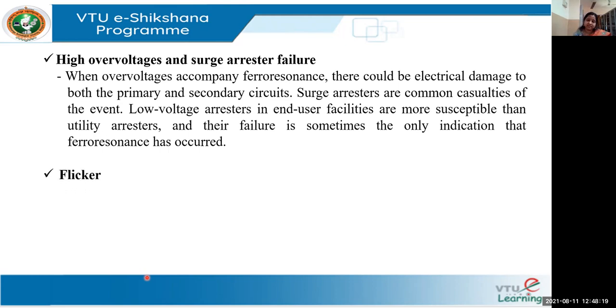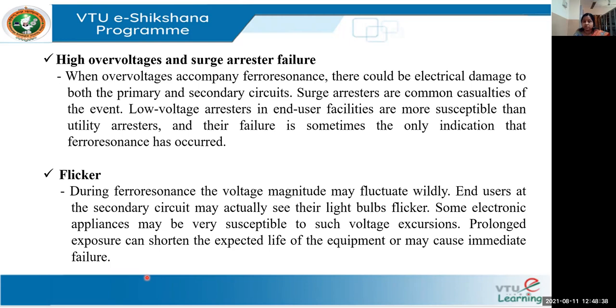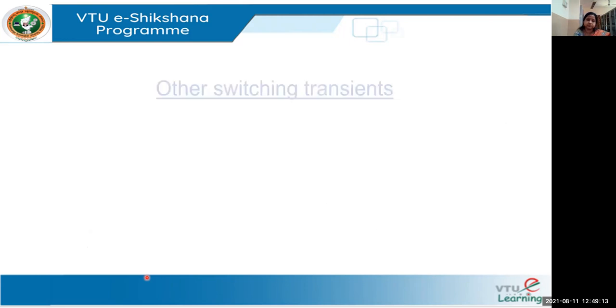Fourth, flickering. When there is a sudden inrush of current or the voltage increases to a very high value, you can notice the lights becoming dimmer. During ferroresonance, the voltage magnitude may fluctuate widely, and users at the secondary circuit might see their lights flicker. Electronic appliances are very susceptible to such voltage excursions, and too much flickering will automatically reduce the lifespan of the equipment.